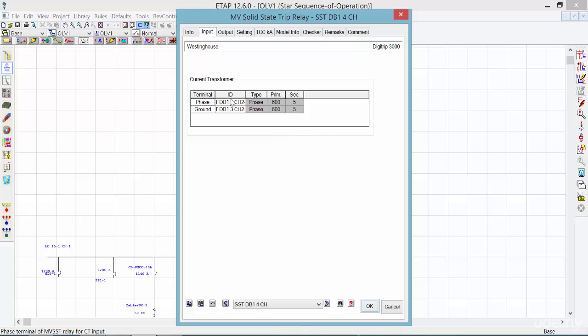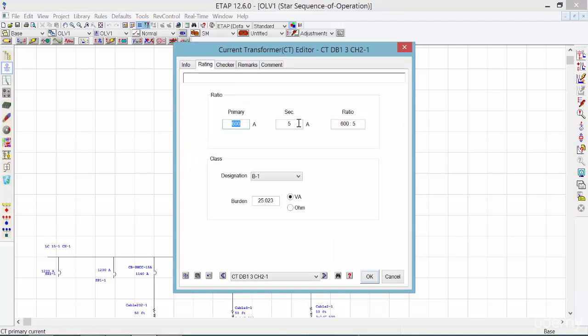What it does, as you can see, it is watching the current transformer CTDB1 3CH2, in which the primary side is set to 600 amp, and the secondary side is set to 5 amp. And again, let's go back and double click on the current transformer. What you can see here on the rating tab is the ratio of the primary and secondary of the current transformer, which is set to 600 to 5, and the ratio is 600 to 5.